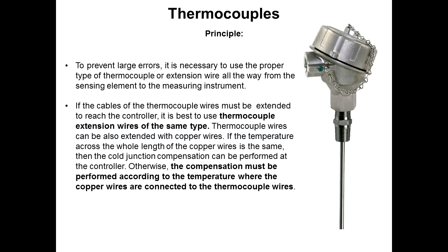If the cables of the thermocouple wires must be extended to reach a controller, it's best to use thermocouple extension wires of the same type. If you use a Type K thermocouple as a sensor, you should use Type K thermocouple wire for your extension. If that's not possible, you can use copper wire to go from a thermocouple to your controller, but the whole length of that copper wire has to be the same temperature as your cold junction, so the compensation can be performed at the controller instead of where the copper wires and the thermocouple wires are attached.